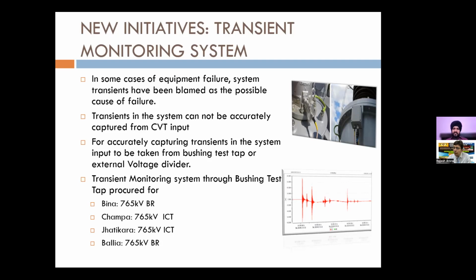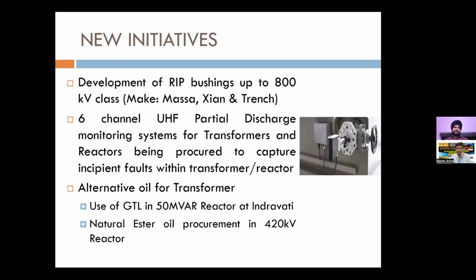Such equipment we have used, and it has been very helpful to us, and we have been able to monitor a lot of transients. But much more needs to be done, because we are still also learning about this type of transient monitoring. So more work needs to be done, and if more data is available, then I'm sure that more things will come to light sooner. Then we have also developed RIP bushings up to 800 kV class. So as on date, Massa and Trench make RIP bushings are already in service, 800 kV.